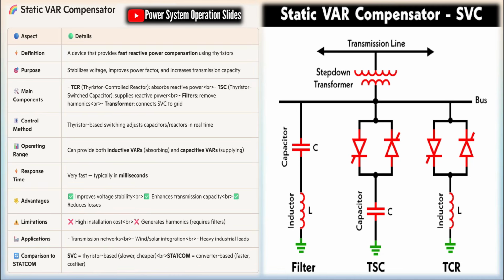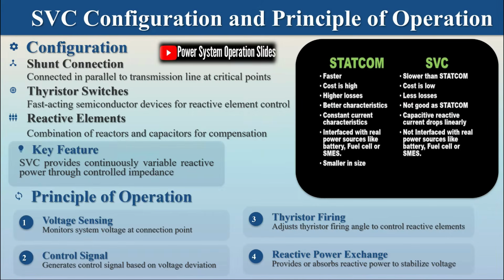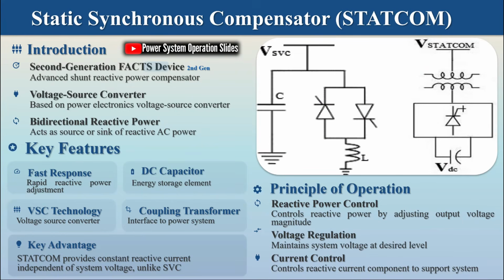The comparative analysis between SVC and STATCOM reveals several key differences in performance characteristics, operational capabilities, and application suitability. One of the most significant distinctions is the voltage current, VI, characteristic of each device. An SVC exhibits a drooping VI characteristic, meaning that as the system voltage decreases, its reactive current capability also decreases. In contrast, a STATCOM maintains a relatively constant reactive current capability over a wide voltage range, providing superior performance during voltage sags and other disturbances.